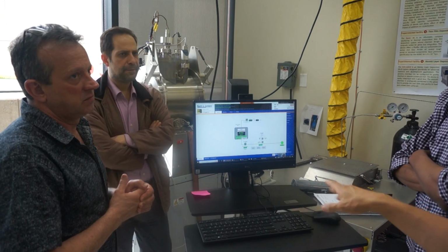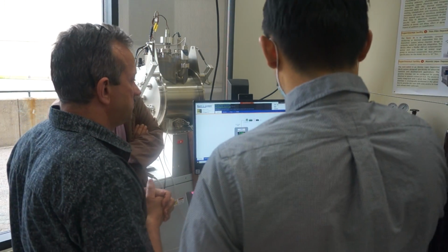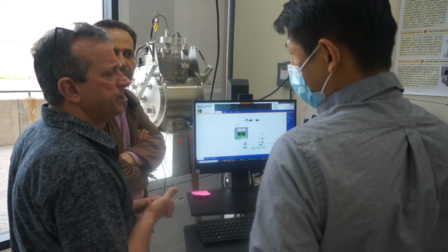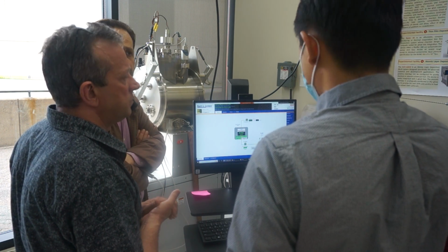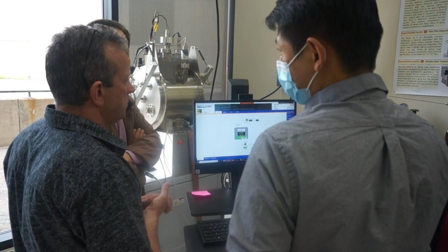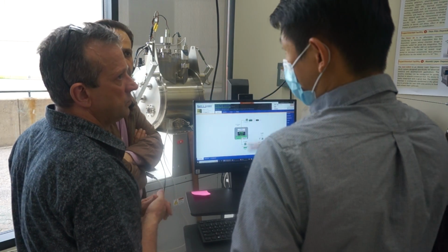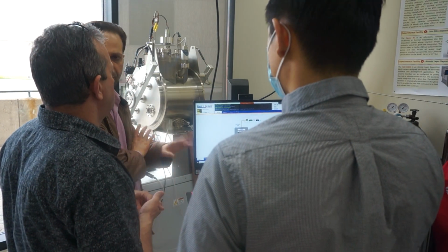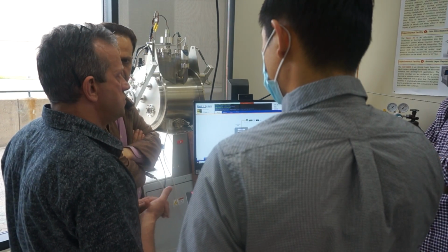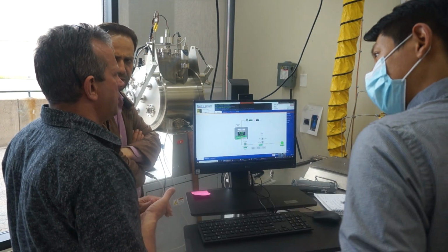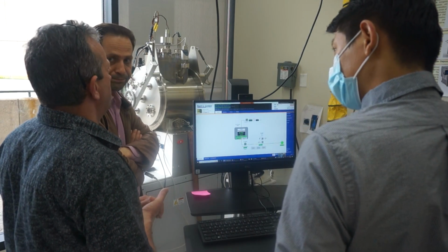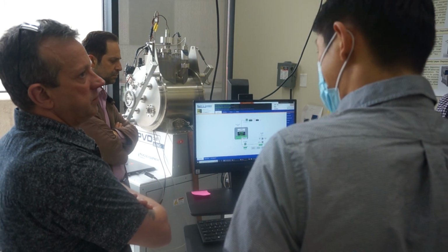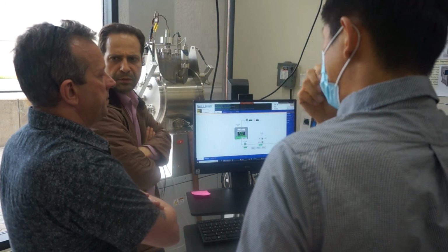So I said, in general, the current setup will work for most of the metal oxide. Right, oxide. Okay. What about ceramic? Because you need RF sputter for that. So the current setup doesn't work for ceramic? Probably not. Not that I'm aware of. That would be a Bruce question. Okay, so that's something that requires an upgrade, or is it just better off using that?